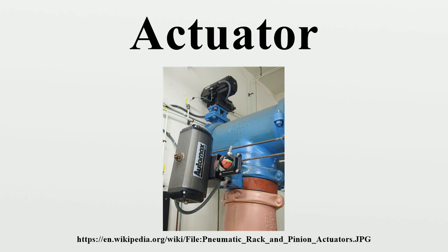Static load is the force capability of the actuator while not in motion. Conversely, the dynamic load of the actuator is the force capability while in motion. The two aspects rarely have the same weight capability and must be considered separately. Speed. Speed should be considered primarily at a no-load pace, since the speed will invariably decrease as the load amount increases. The rate the speed will decrease will directly correlate with the amount of force and the initial speed.